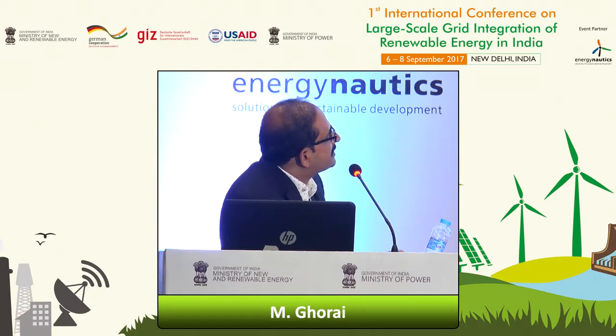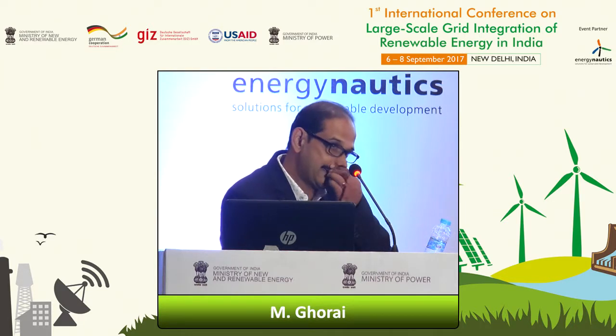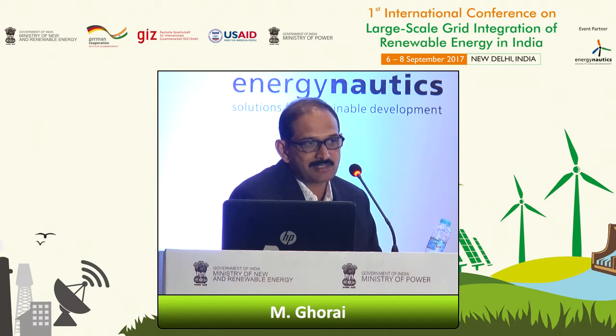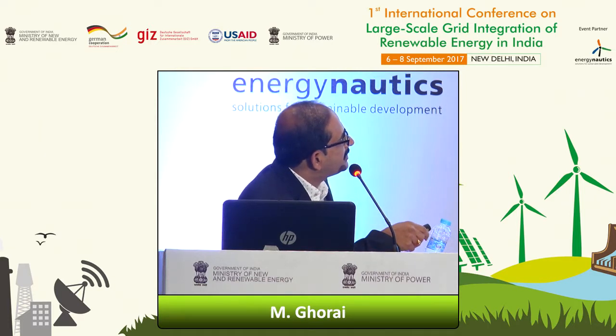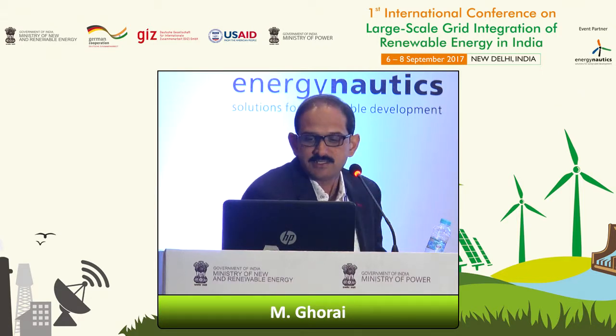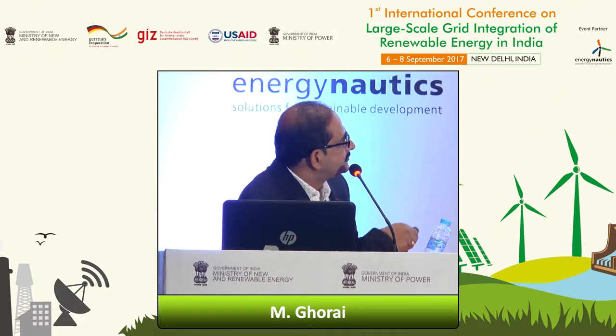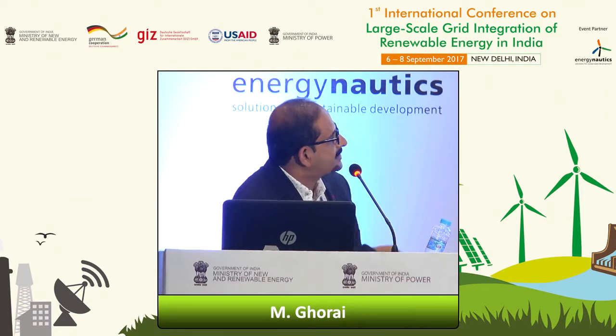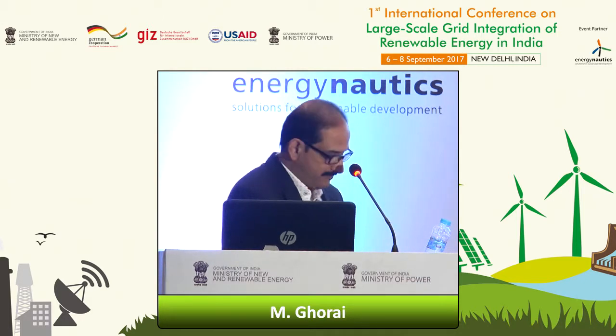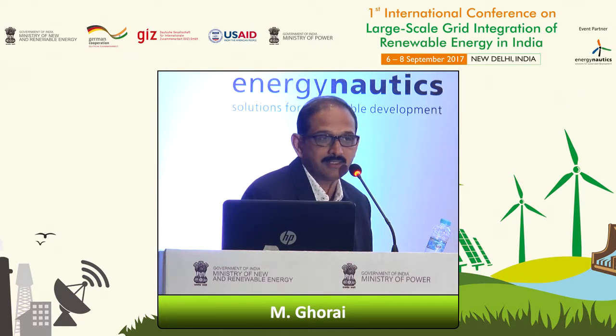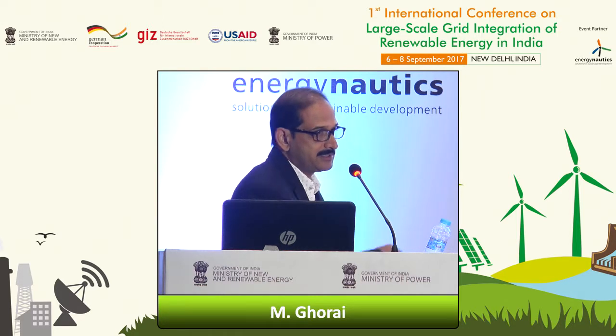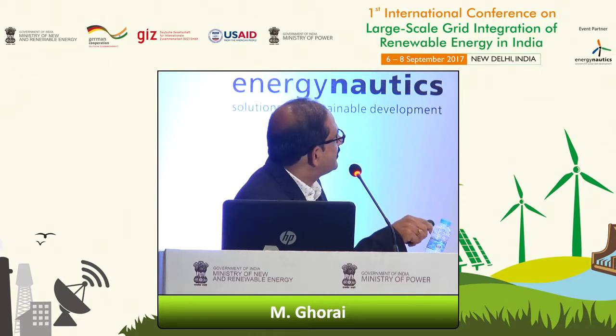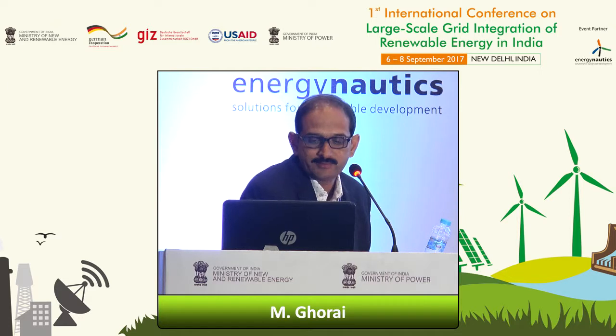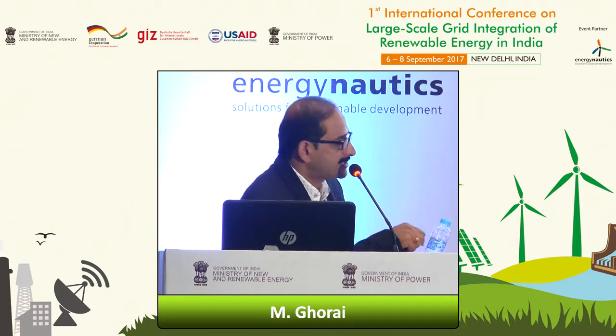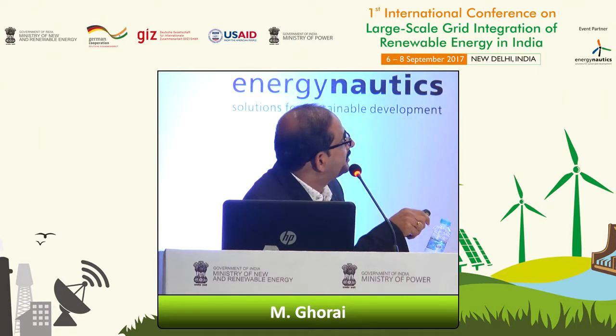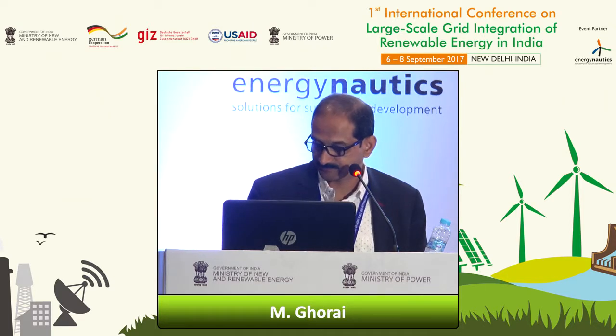On the dynamic side, they have a requirement of reactive current injection, especially when there is a deep swell or sag. They want you to inject current in this manner, going even up to the zero level. And there are also the LVRT and HVRT requirements. I'm giving an example of one of the wind farms in South Africa, where again after studies we found that a STATCOM is required. STATCOM was provided for this wind farm, and we used a single master control cabinet to control the requirements at the PCC.